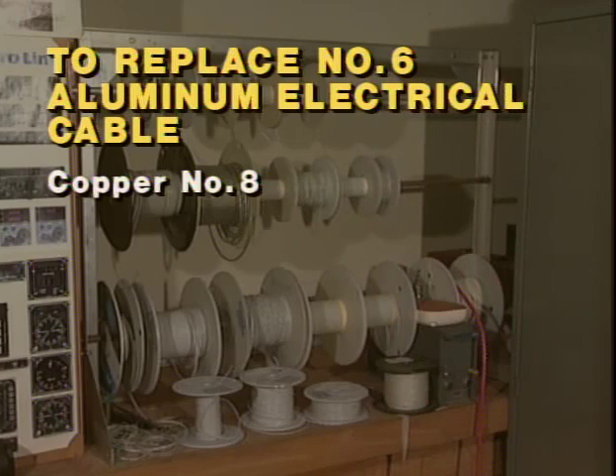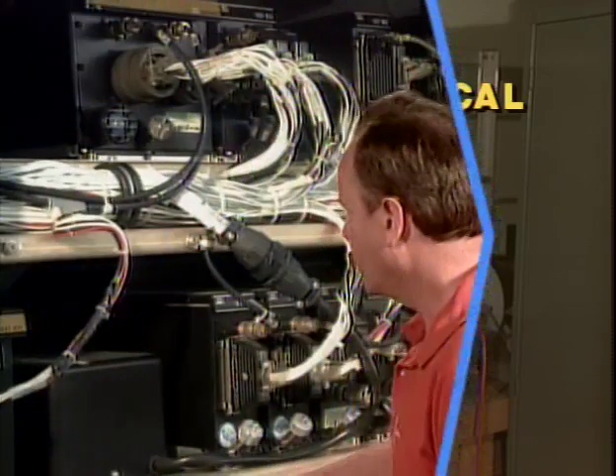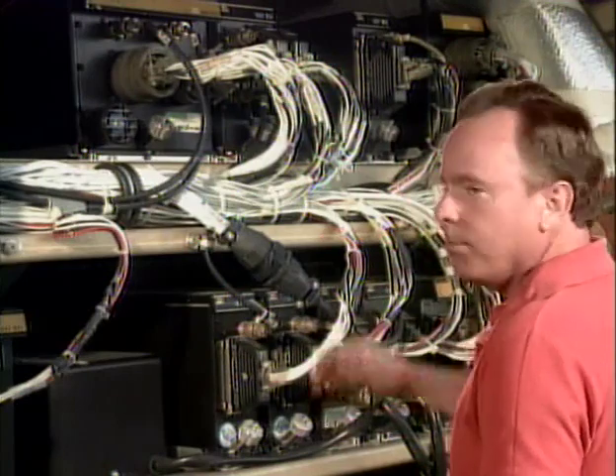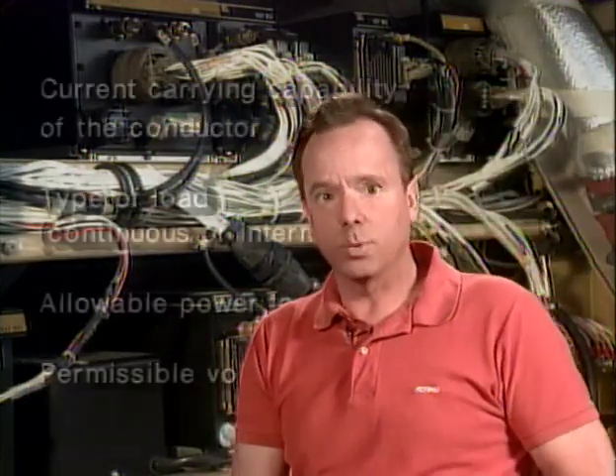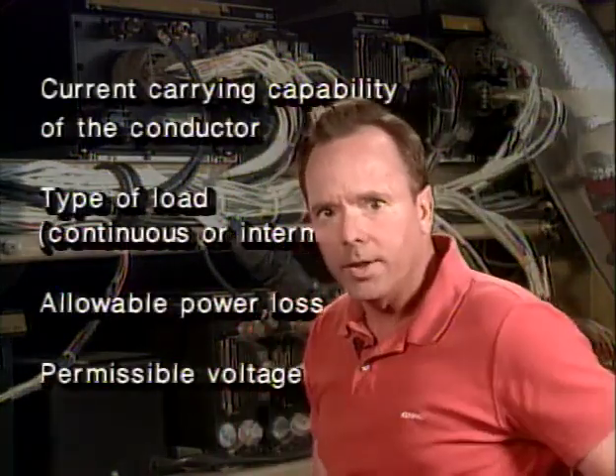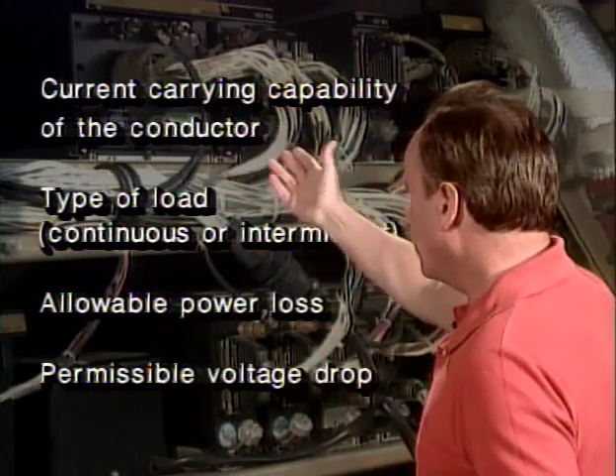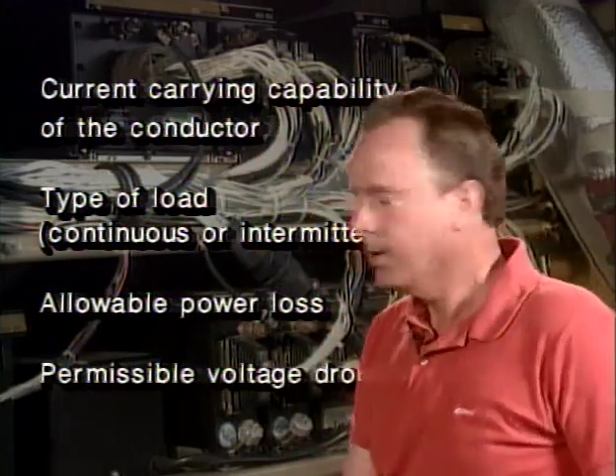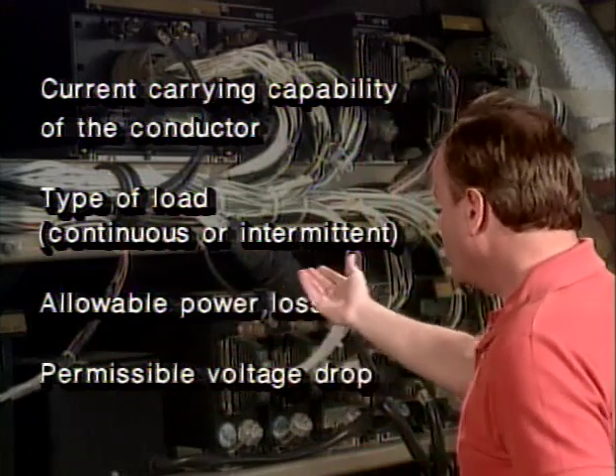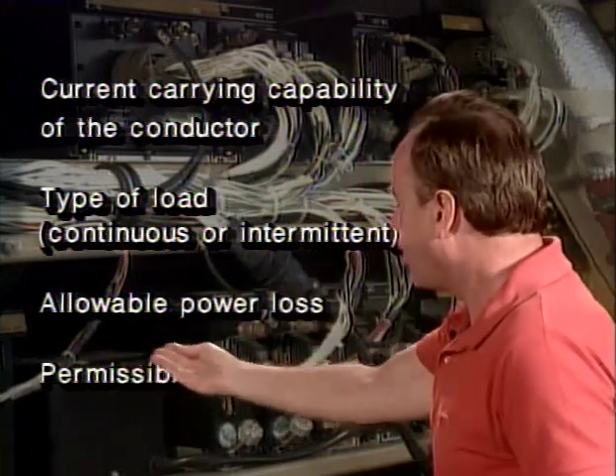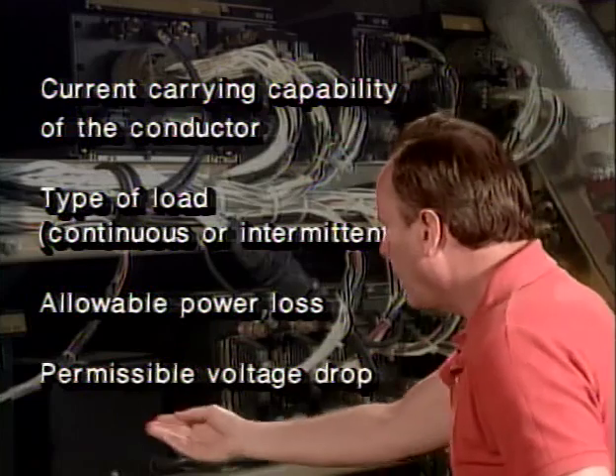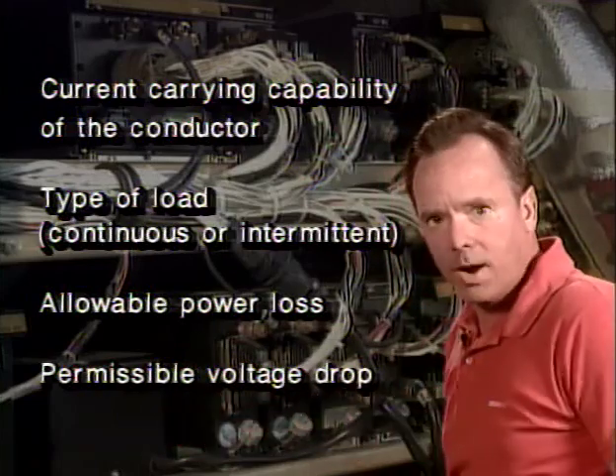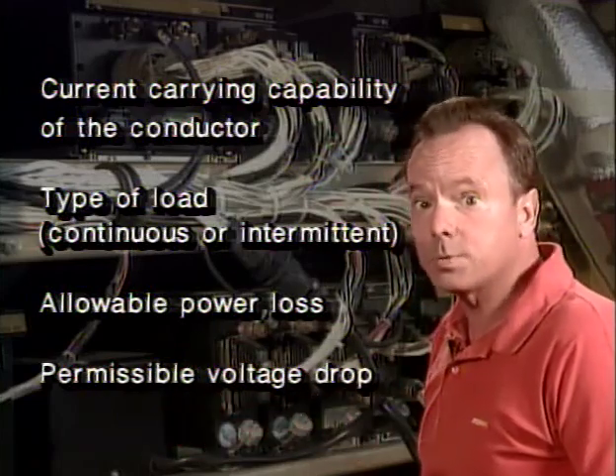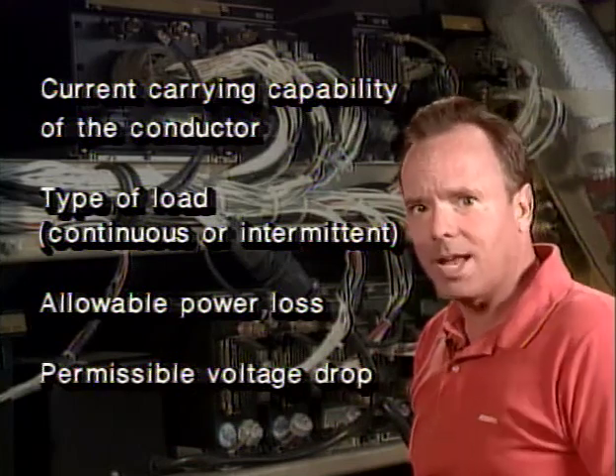Now let's take a look at the primary considerations when you're selecting electric cable size. So you want to pick a wire cable and pick a certain size. What are the considerations? Well, let's take a look at them. First of all, the current carrying capability of the conductor. Can it carry the current? Next, the type of load. Is it continuous or intermittent? Next, allowable power loss. And finally, permissible voltage drop. So these are the primary considerations when you're selecting electric cable size.